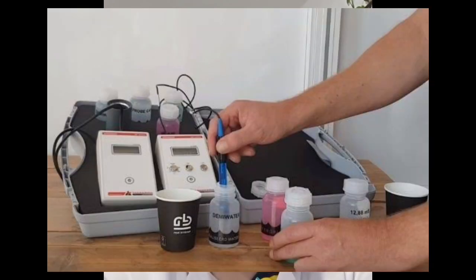It starts by plugging the pH meter into the power supply. Once turned on, the equipment is calibrated with the 3 buffer solutions. This is done by removing the electrode protection, rinsing with distilled water over a beaker, drying with a delicate paper, and immersing the electrode in the buffer. Wait for the pH to stabilize and for the screen to indicate that it is correct. The electrode is removed, rinsed, and dried. This process is repeated in each calibration solution and for the analysis of solutions.